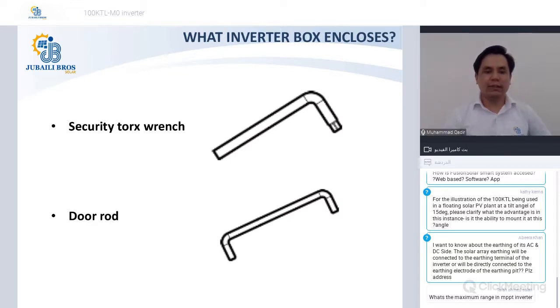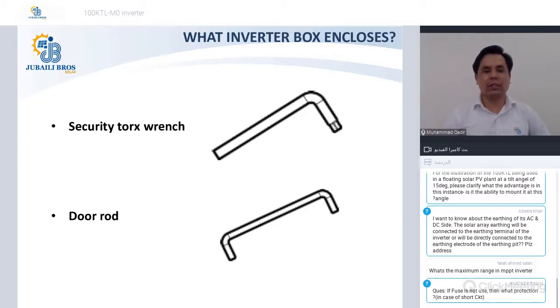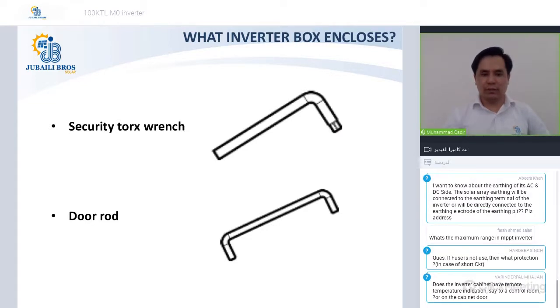Further, you will find a security torx wrench. So if you want to open the inverter, or the maintenance compartment, which is the point where you will be connecting your solar cables, sorry, the AC cables, you will be using the security torx wrench. Otherwise, you can use your own torque wrenches as well. Huawei does not recommend you open the electronics compartment. That is fully sealed, and it comes with a seal on the sides. If those seals are taken off, the warranty may get void.